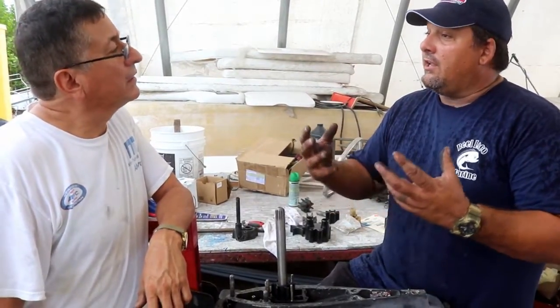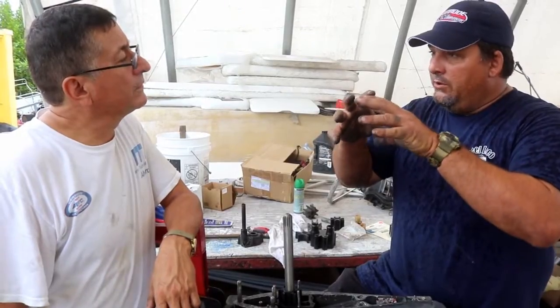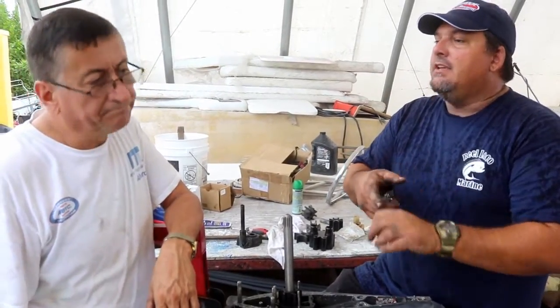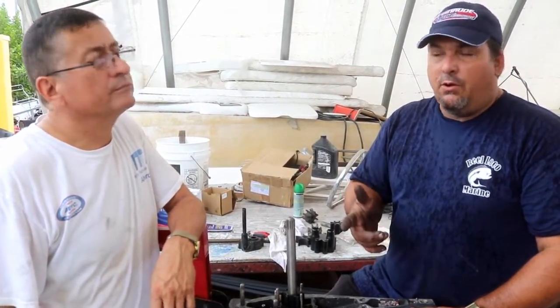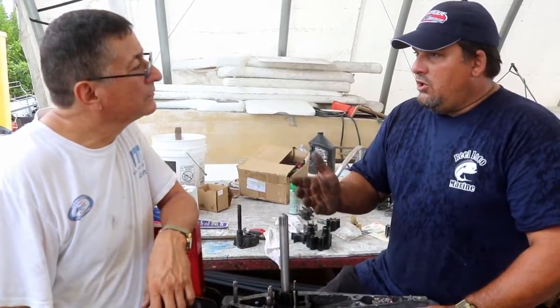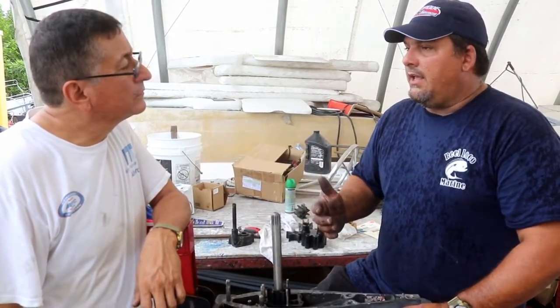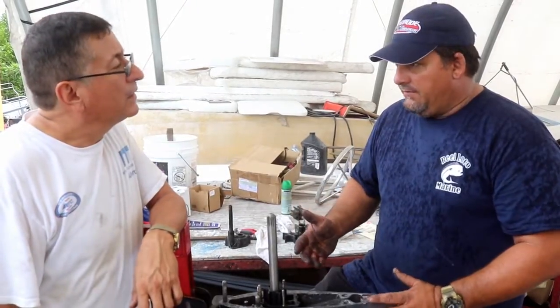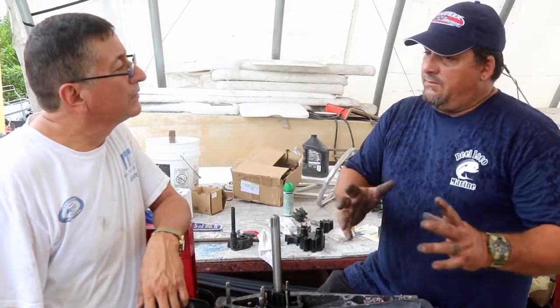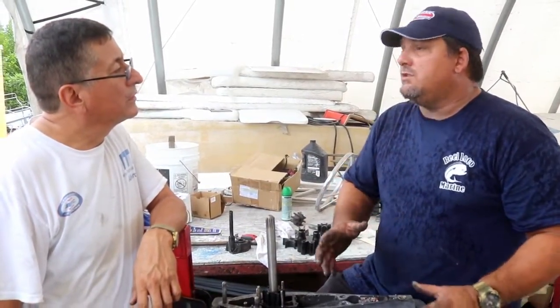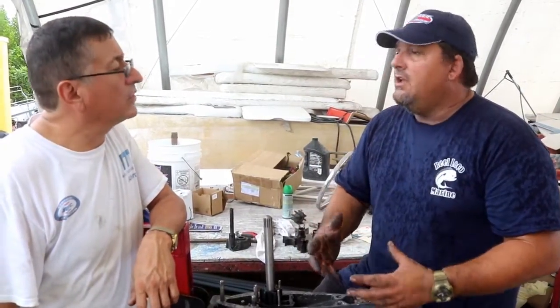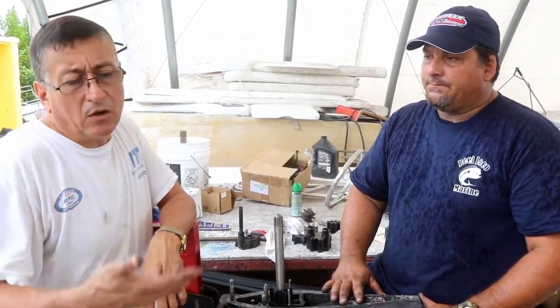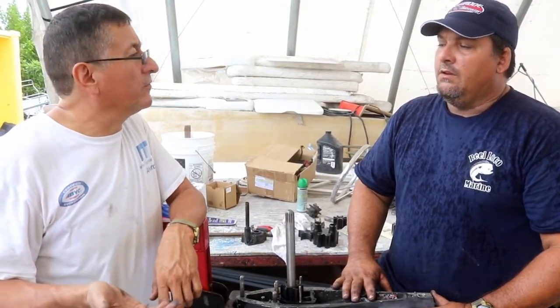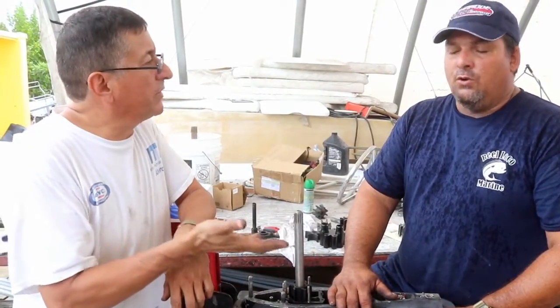That causes crevice corrosion, it builds up salt, binds the bolt, and when you try to remove it later you'll snap it. So if it's your customer and you know you'll work on it again, apply grease to everything, unless it's a bolt that takes Loctite, in which case you obviously don't grease it. Otherwise, as a rule of servicing, you should always grease it, or use the lubricant recommended by the manufacturer, since each manufacturer has its own specific lubrication recommendation.